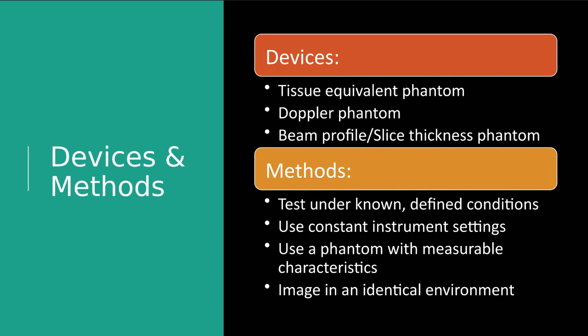So you have to be doing this under really controlled situations. If your room is typically set at 70 degrees, you don't want to have QA come in and drop the AC down to 50, right? Because that's not what your machine typically operates at. So you want to keep the entire environment standard. We want to be testing under known defined conditions. We're using constant instrument settings, so we're not taking a transducer from a different machine and using it on a machine to do QA.